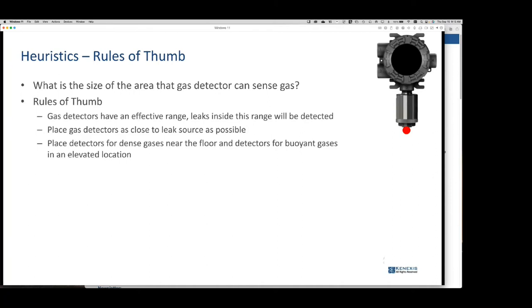But that 7, what happens is when a gas cloud gets bigger than 7 meters, you have a much higher risk of having a vapor cloud explosion, having a pressure wall when that thing ignites great enough to cause damage, blow people off a platform, stuff like that. So they at least did the research to come up with that. Here's what's really interesting. Historically, over time, they found out that there are a whole bunch of platforms at sea now that have a 5 square meter grid. People still call us and say, hey, you can do anything you want. We don't care. Just put them on a 5 square meter grid. And we're like, well, can we discuss it with you?